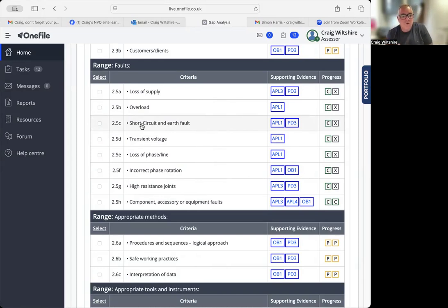But let's talk about this. Let's say, for example, you've encountered a short circuit, you've put your photographic evidence in, it's tripping off, you've safely isolated it, you've done insulation resistance testing, you've got 0.00 on your meter, you've split the circuit down, found the fault, showed us the fault, re-terminated it, retested it, happy days. So that's your picture sequence. Absolutely great, right? So we know the story of the job, yeah?